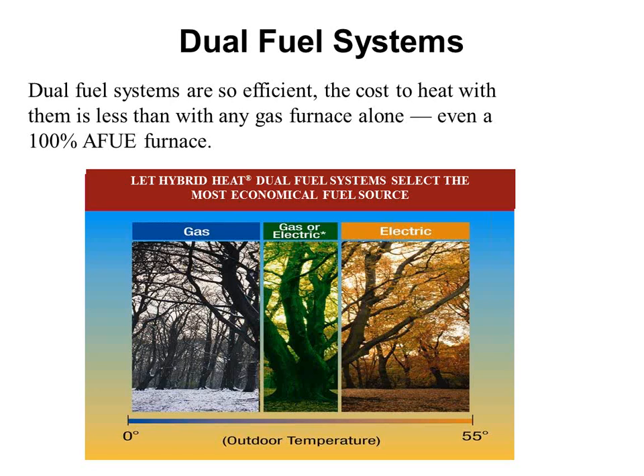The thing we do a lot now in the past 10, 15 years is we combine heat pumps with a gas burner as well. So it can be a natural gas or a propane or theoretically even an oil burner. We combine those two systems, so when it's a mild temperature, 20, 30, 40, 50 degrees outside, run the heat pump. When it's below those temperatures, say 10 degrees, 0, 15 degrees, run the gas furnace, right? Kind of get the best of both worlds. Be able to handle the heating capacity that I need and be able to be reasonably efficient when it's super cold outside. And then when it's mild outside and the heat pump can be more efficient, we'll look at doing it that way.